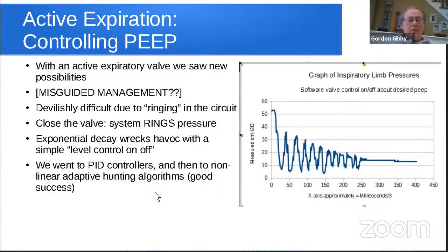Okay, so now, because of this new design that Al Winsenreid had come up with, we now had an active expiratory valve, and we could control both inspiration and expiration separately. And maybe we made a mistake by doing this in retrospect. We thought we were doing what the FDA wanted. When we tried to control the expiratory valve, we learned that the system would ring. Oh gosh, it was just huge ringing. The air would move back and forth, and our pressure sensor would read this pressure and then that pressure. They would open and close the valve and drive us nuts. On the right of this screen, I give you a plot of what the inspiratory pressure actually looked like in the ringing system. We basically had a nonlinear system, and it could oscillate like the devil.